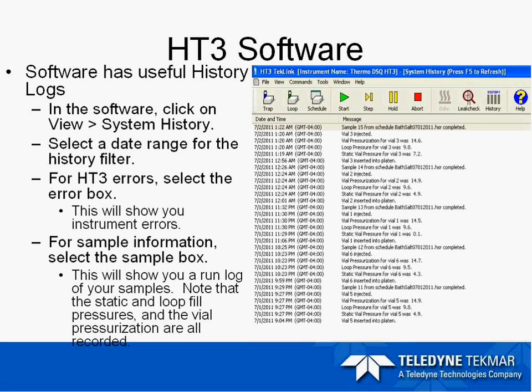After each scheduled run, a unique vial file is created — this only happens when a schedule is completed. This is stored in the data folder on the hard drive directory of the TekLink software. It provides detailed information on each schedule run, including all the information in the system history, all your method parameters, what firmware versions were run, and any additional information for that method.